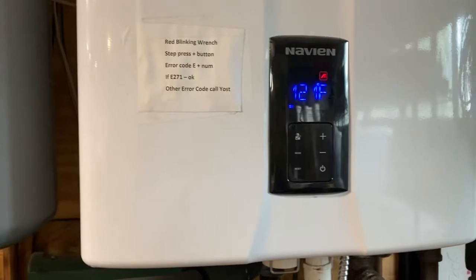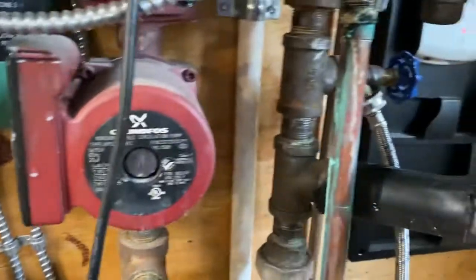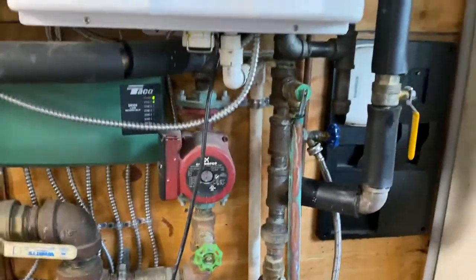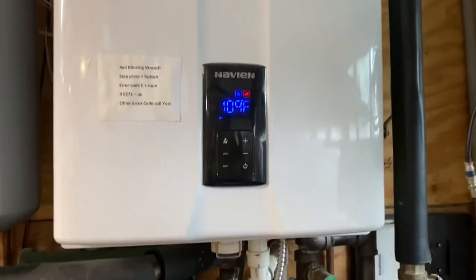And that fixed it, so this is the same thing that happened before — after I drained it. The draining process was: close this valve, open that valve to drain, and then reboot by a hard reboot of unplugging the Navien. And that seemed to work.